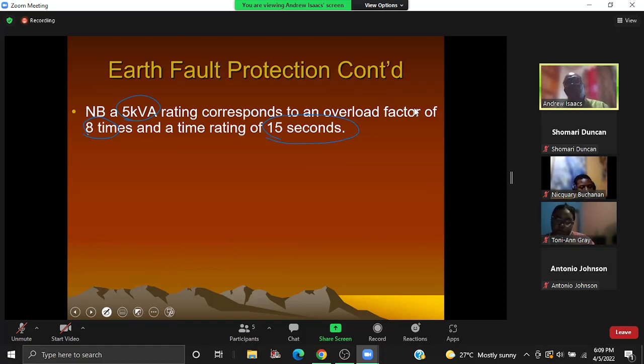So what's the key takeaway here? In selecting the transformer in terms of its capacity, you'll be looking at the maximum possible voltage, you'll be looking at the maximum current, you'll be taking into consideration any derating factors that are applicable. So for the 6 times, you can do 30 seconds. Yeah? For the 8 times, you can do 15 seconds. Maybe if you go to 10, it might drop you to 10 seconds. All right?